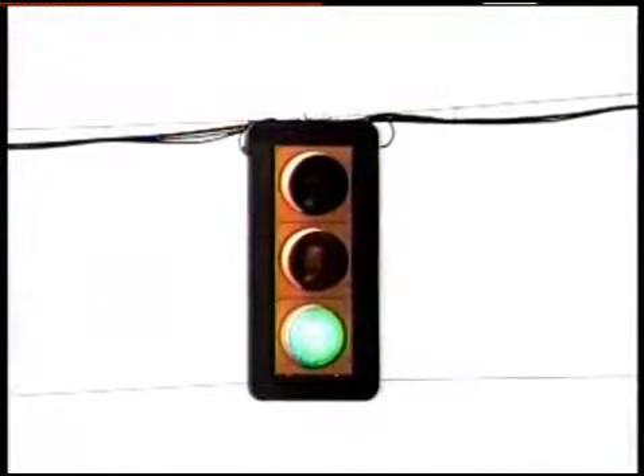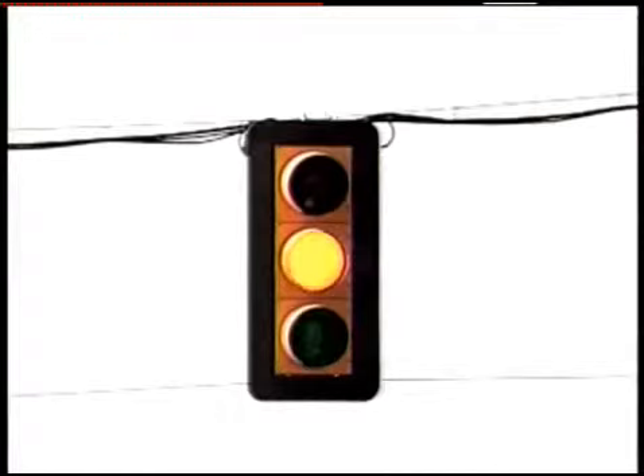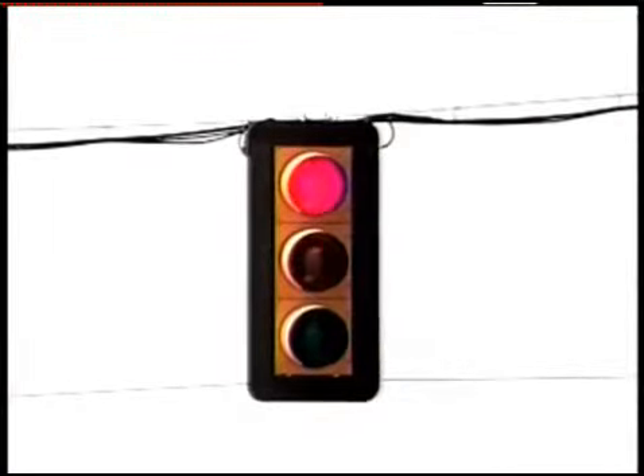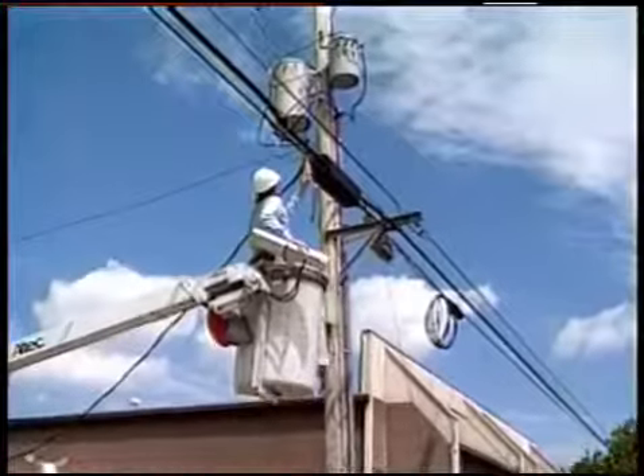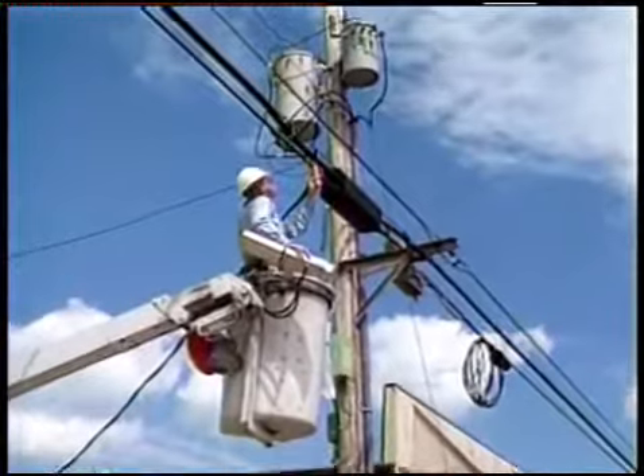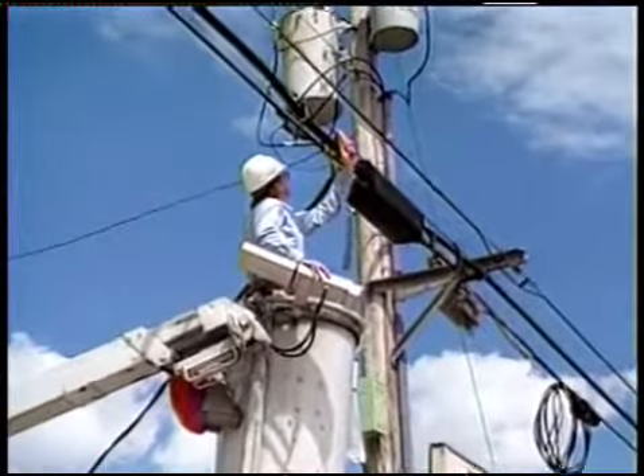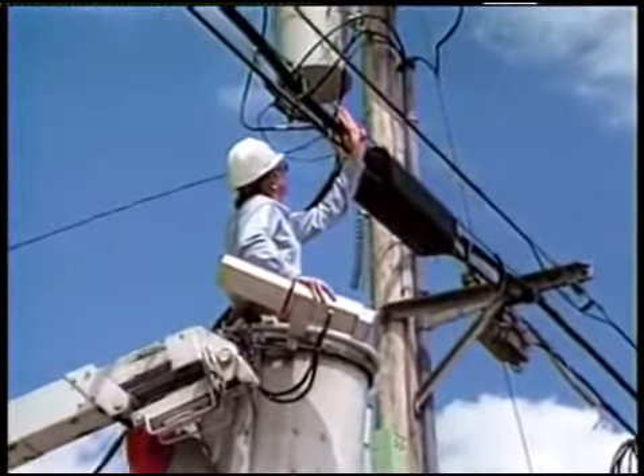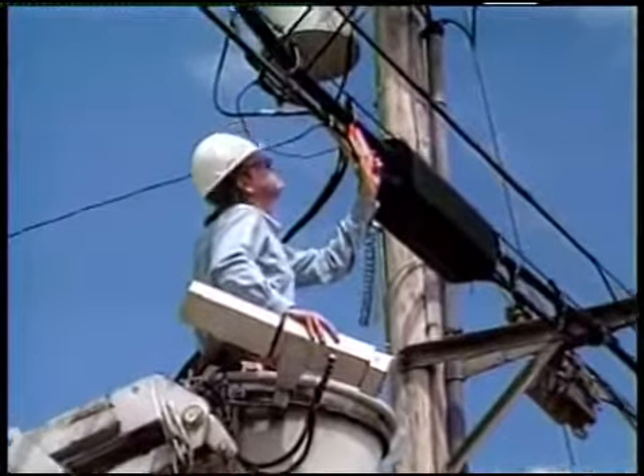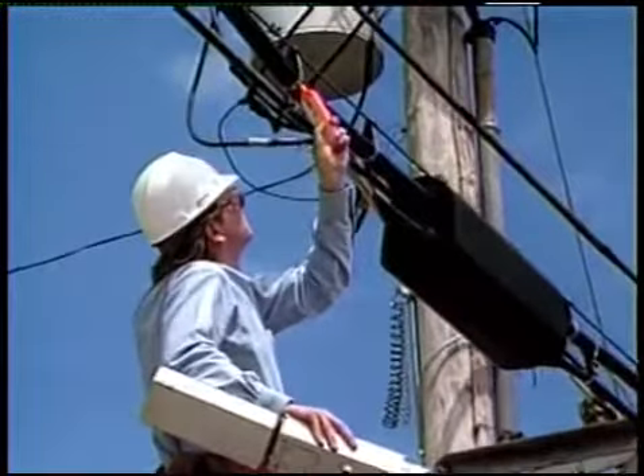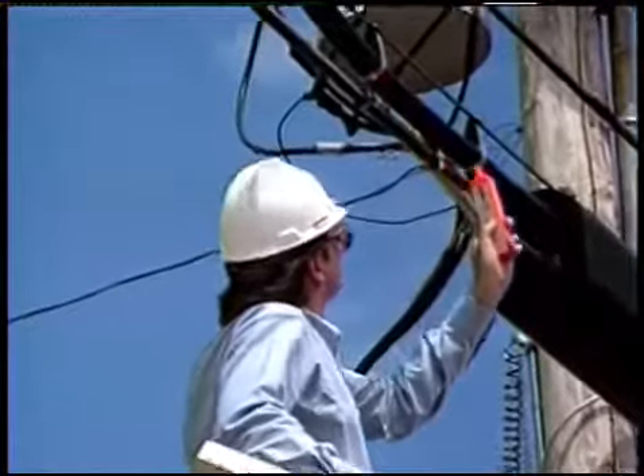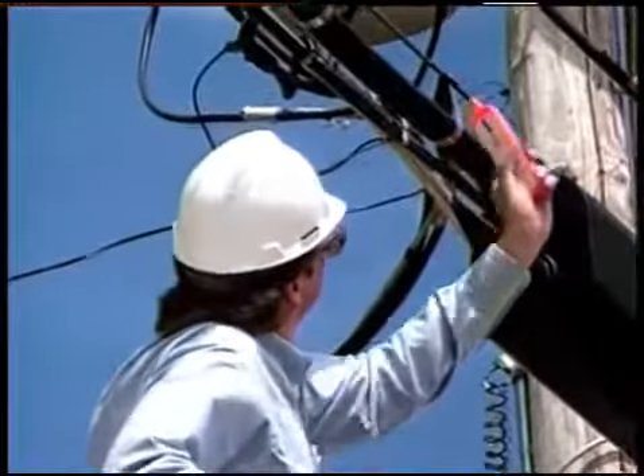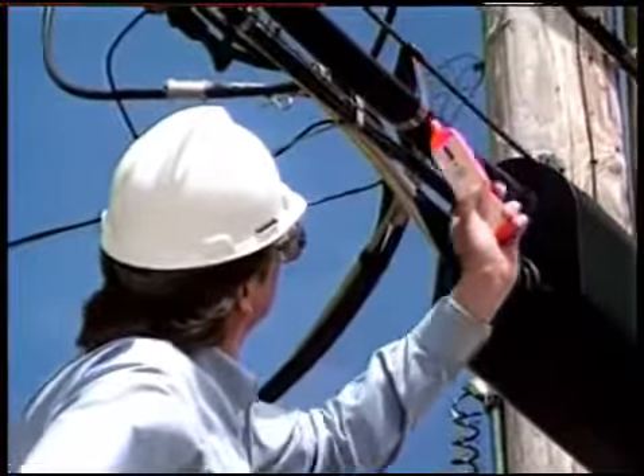When testing a device that is cyclic in nature, such as a traffic light support strand, the operator should always test through at least one complete cycle. This will avoid missing detection of a fault that occurs on a single phase of the cycle. In summary, the F.V.D. has been designed to overcome many of the limitations of previous test sets. The small size and ease of operation make it a very useful tool. However, no tool can be of value if it is not used. Keep the F.V.D. with you and use it at every opportunity you have.